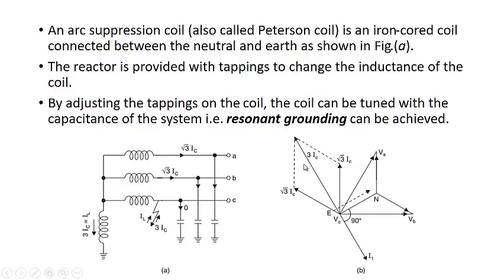You can see they balance each other, and the net current that flows through this will be equal to 0, and there will be no arcing and there will be no over voltages. So by adjusting the tappings, the coil can be tuned with the capacitance of the system, that is, resonant grounding can be achieved.